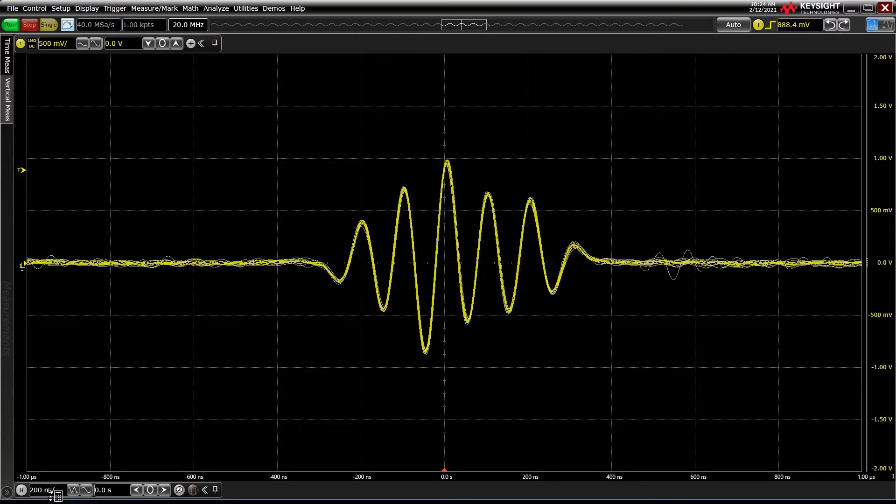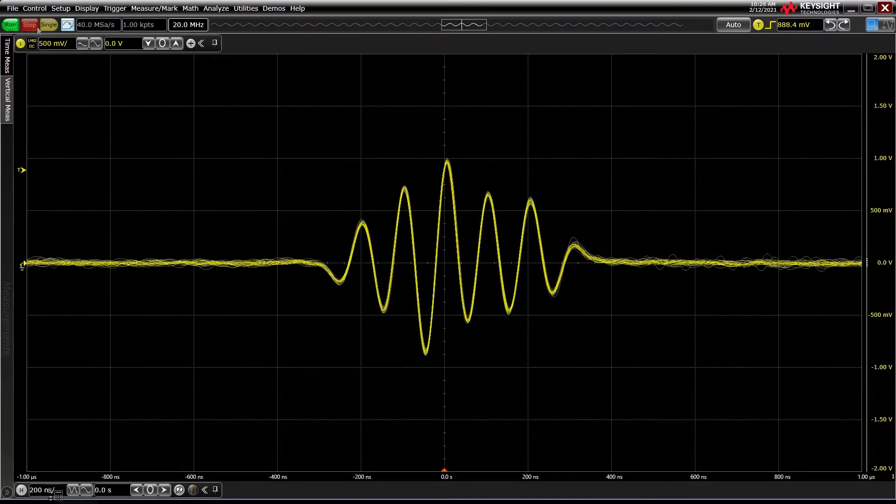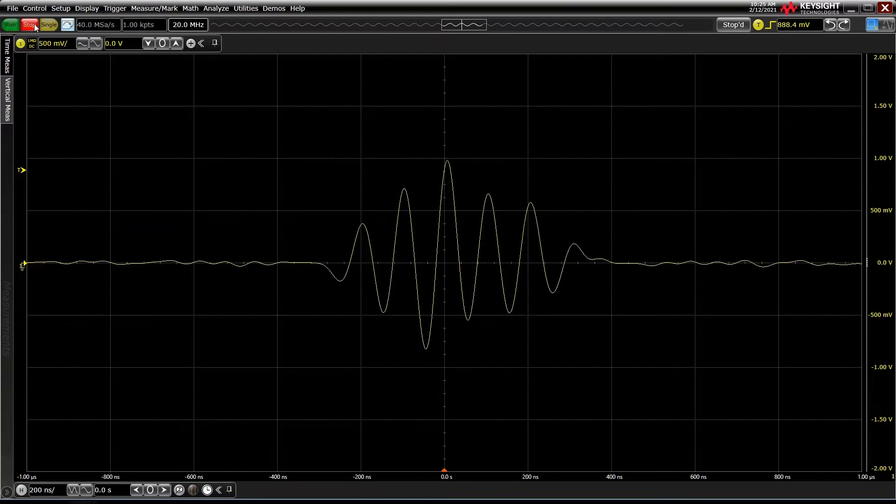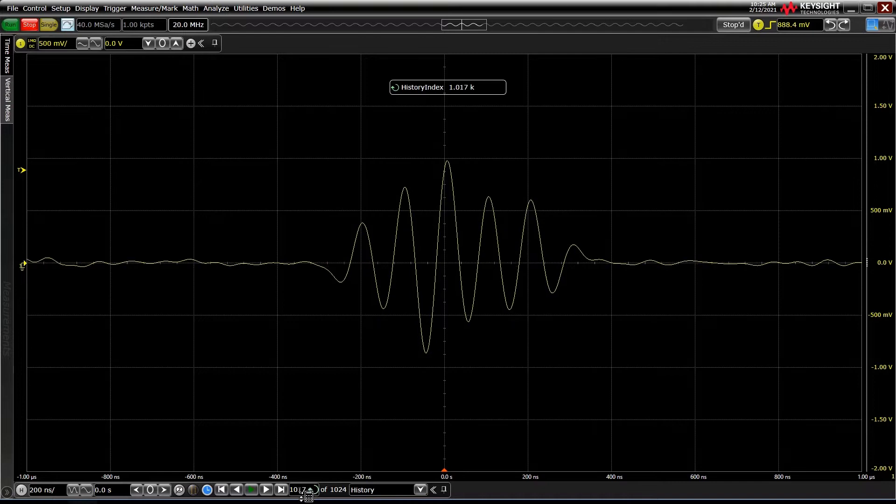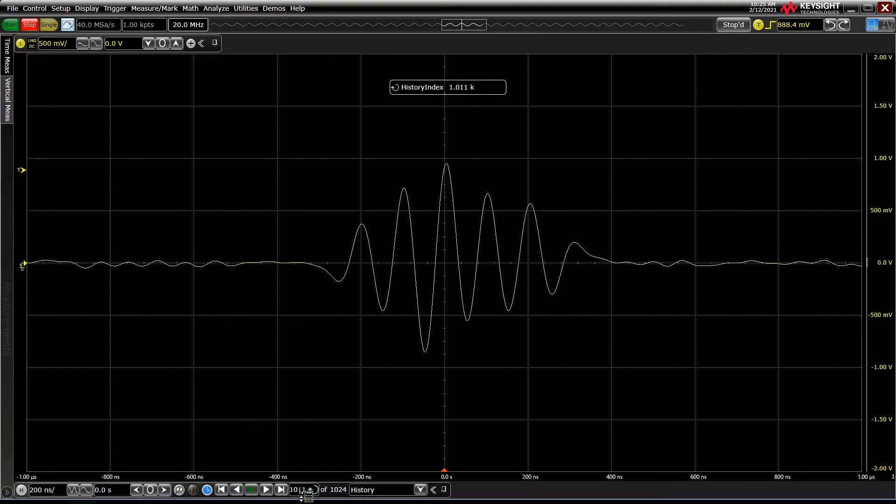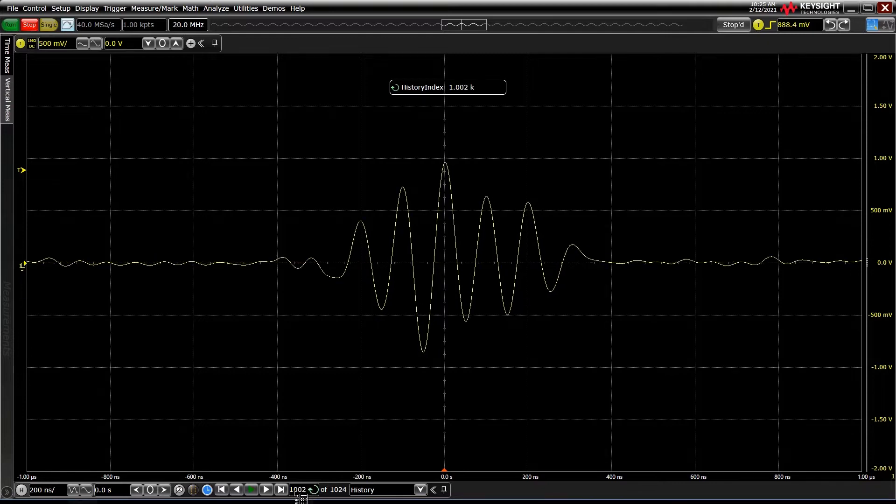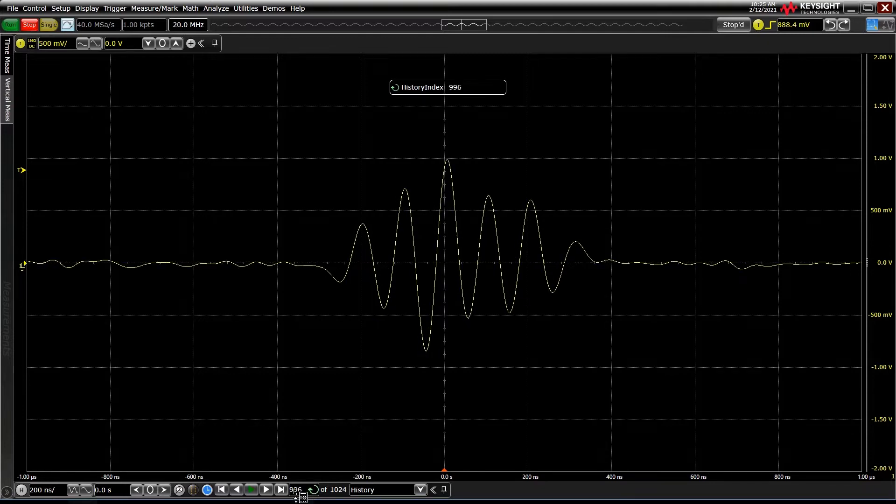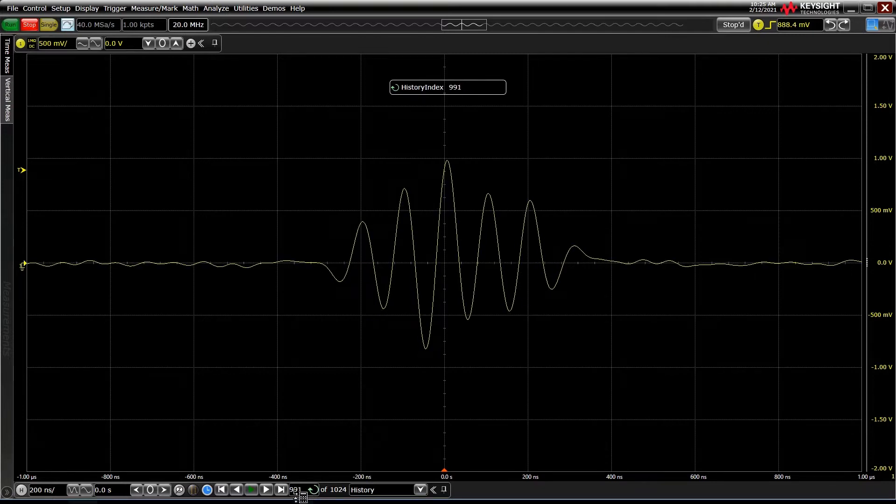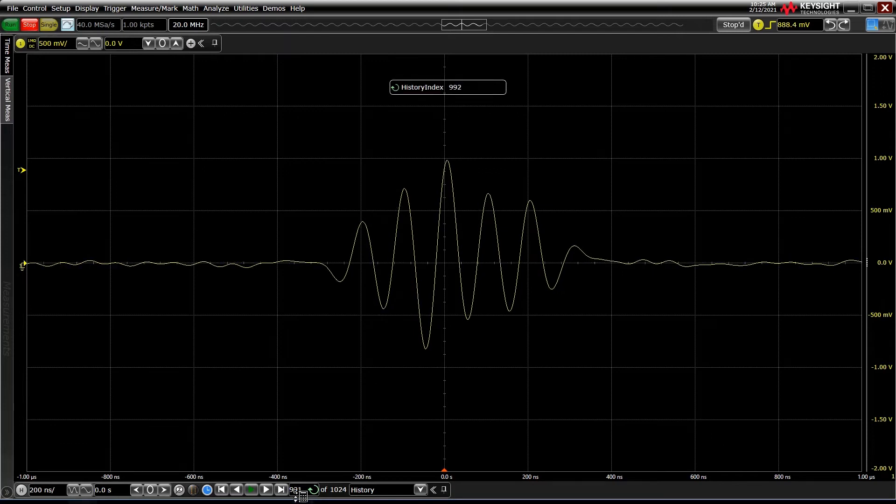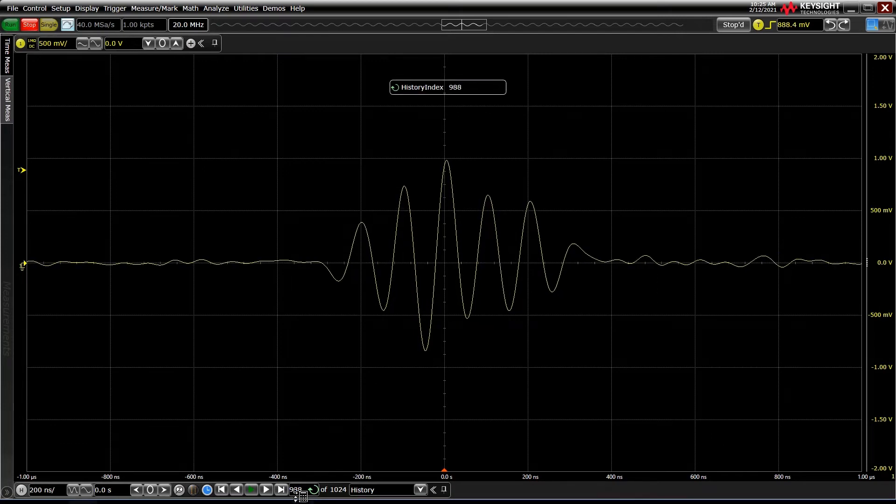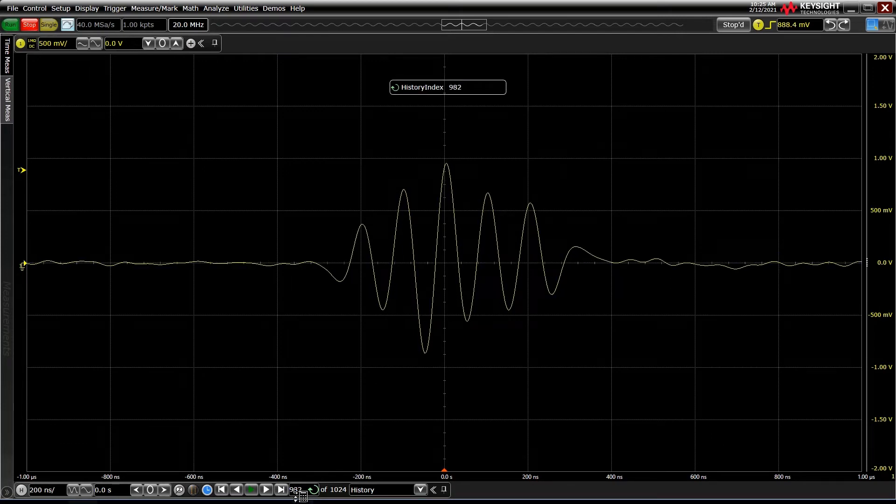With the all-new history mode, the oscilloscope uses a cyclical memory buffer to capture up to the last 1,024 trigger events before the oscilloscope is stopped. This is helpful if you see something pop on screen, but it disappears with the next trigger event before you can stop the oscilloscope.